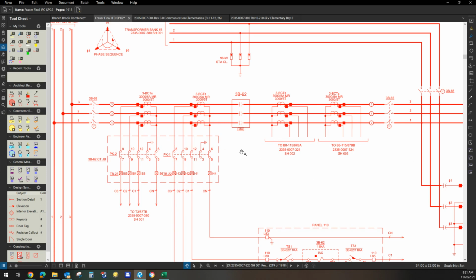Of course, you can verify that with the nameplate information on the drawing and the nameplate information on the door at the breaker. I notice here on pole 1, on the bus side, I have 2 CTs stacked. This one is on top of this one. And on pole 2, I have 2 CTs stacked. This number represents the pole, and this is the physical top of the pole.